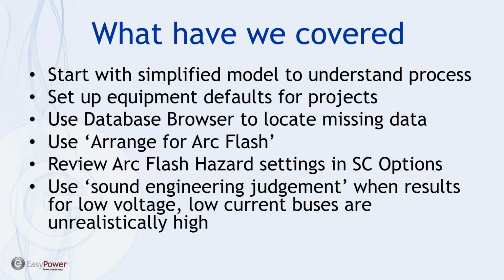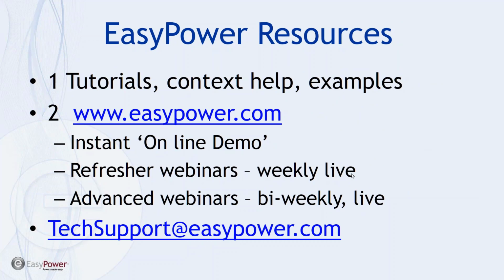Okay, so what we've talked about today is we want to start with a simplified model to understand the process. When possible and when it's productive, set up equipment defaults for the project to have known values entered in when we first build the one line. Utilize the database browser to locate missing data from a 5,000-foot view. Use arrange for arc flash to make sure we understand the available fault current and which upstream tripping device is in play for any particular bus, especially if it doesn't make sense on an initial viewing, and utilize the arc flash hazard settings and short circuit options to make sure that it matches what we're trying to do in our calculations. And above all, use sound engineering judgment when the results for low voltage and low current buses are unrealistically high.